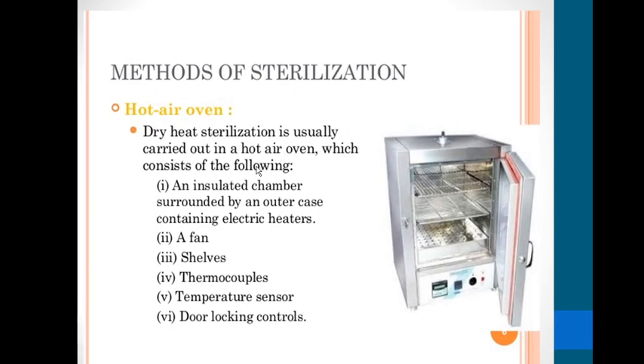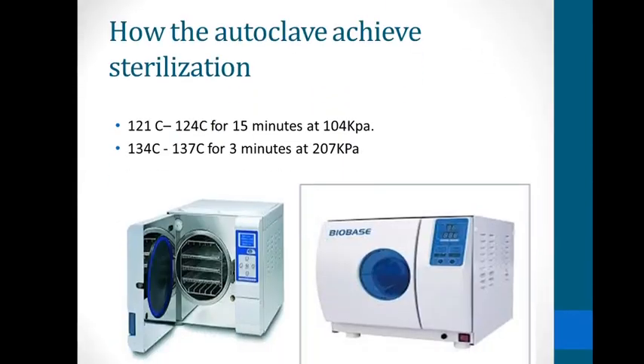Dry heat sterilization is usually carried out in a hot air oven, which consists of the following components: an insulated chamber surrounded by an outer case containing electric heaters, a fan, shelves, thermocouples, a temperature sensor, and door locking controls.